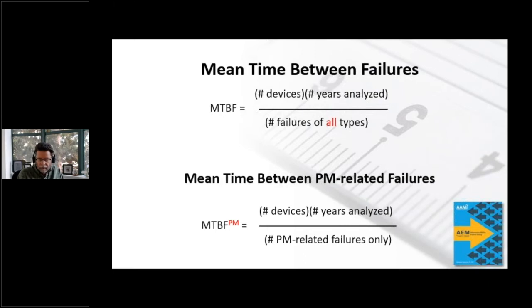I've done some consulting with a group that felt like they were always behind the curve on problems related to certain infusion pumps. Being behind the curve meant they were hearing from users who were losing confidence in the equipment, and it was not showing up in the CMMS data in a timely fashion. So they moved to something along these lines, and their reaction is that this moves them a little bit closer to real time, putting them in a position to be less reactive, or at least more quickly reactive.